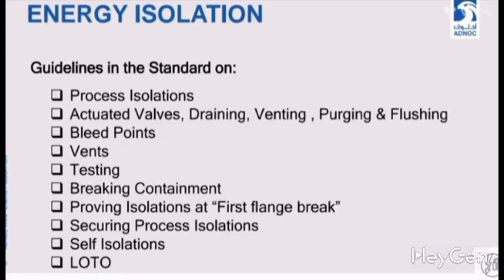What will the vent system be? How do we have to test our isolation, breaking containment? If we have any leakage, how do we tackle it? Proving isolation at the first flange break. How do we perform a verified test of our isolation? Securing the process isolation. How to perform double isolation?